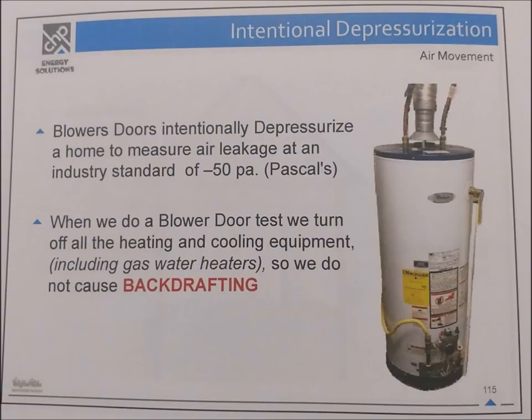Intentional depressurization: Blower doors intentionally depressurize a home to measure air leakage at an industry standard of negative 50 pascals. When we do a blower door test, we turn off all heating and cooling equipment, including gas water heaters, so we do not cause backdrafting.